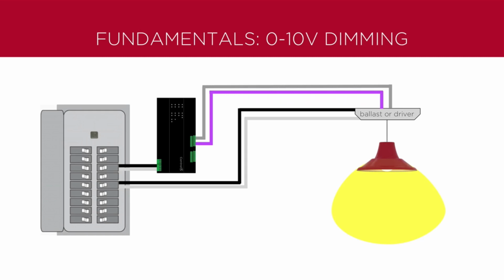0 to 10 volt dimming generally does not include on or off controls. A separate control is usually required. The 0 volt command is the minimum on level, such as 1%. It is not the off command. 0 to 10 volt dimming requires that you switch off the line voltage to the load in order to control the on and off states. This usually requires an external relay. In contrast to fluorescent ballasts, LED drivers usually do have an on and off control.